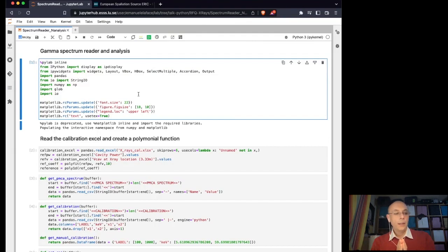Basically, from the RFQ, the radio frequency quadrupole, the first object all in copper that I showed you, we started to put some power without the beam, but we wanted to know the acceleration of this device, how much field it generates. And without the beam, we have no instrumentation inside. So what we did was to exploit the fact that while you power it, some electrons are released inside. The electrons travel inside the device, hit the object, and generate an X-ray. And the energy of the X-ray tends to be the energy of the acceleration, or the voltage, let's say. So from powering the device and from these electrons that are generated by the surface, we were able to estimate, from the energy of the X-rays released outside the device, the power of the device.